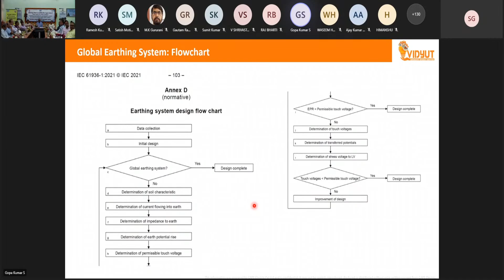If you don't go for a global earthing system, then you have to determine the soil characteristics, the current flowing to earth, and do all these calculations, and finally the permissible touch and step voltage values must be met. A global earthing system can be used in your power generating stations and transmission stations, and so on. If you have a large area like a generating station with different operating voltages, I request you to please go through IEC 61936. Global earthing system is the ultimate solution.